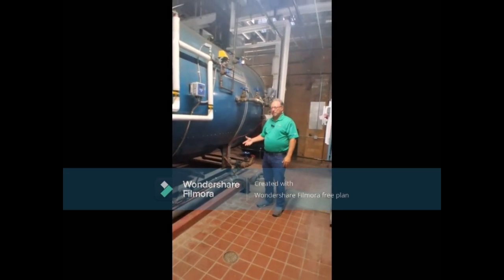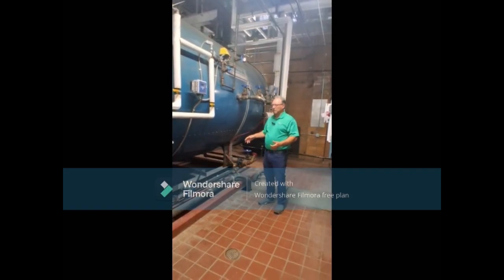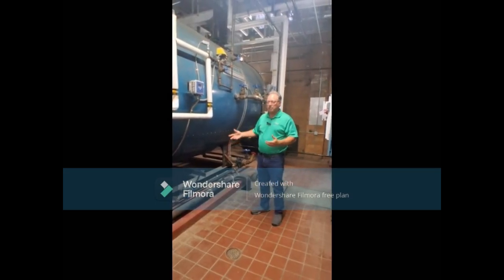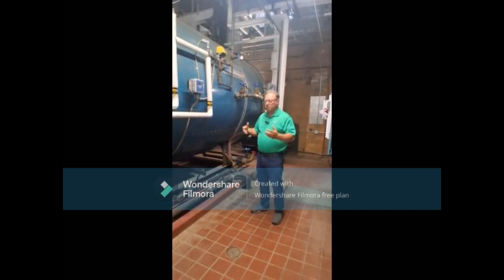So it's important to blow down a boiler to maintain like 3500 conductivity off the blowdown down here, and then on your PMs, when you open your boiler up, take all the sludge that falls down off the tubes and remove it, just like you would any normal PM practice.